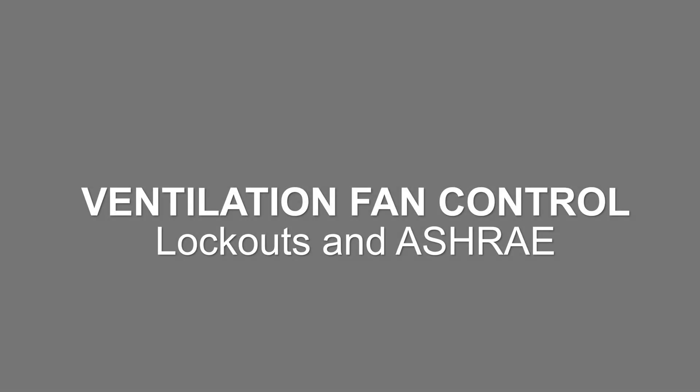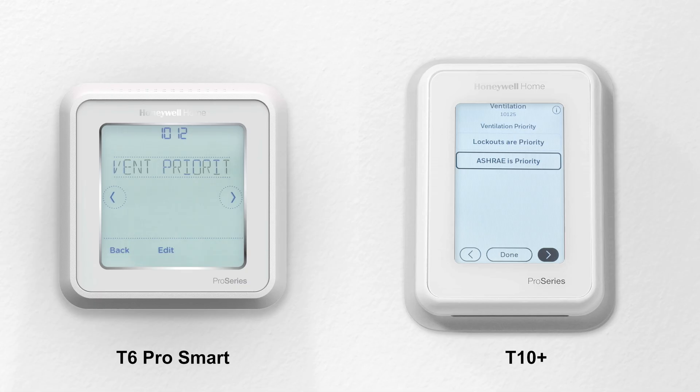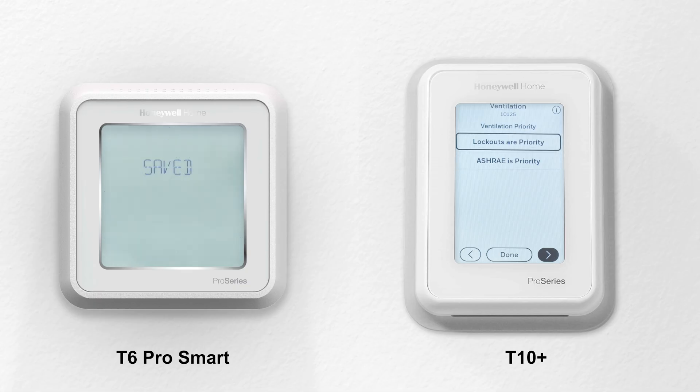Under Ventilation Priority, you can select whether lockouts take priority or ASHRAE takes priority. When lockouts are priority, the thermostat won't run ventilation during lockout conditions. I'll cover setting these optional lockouts in a moment.